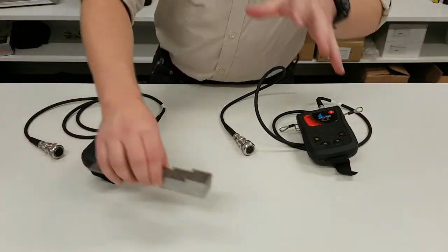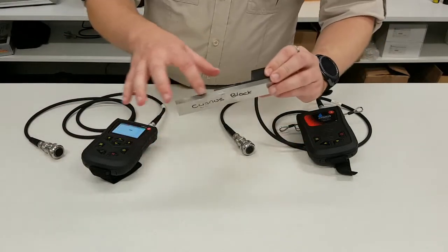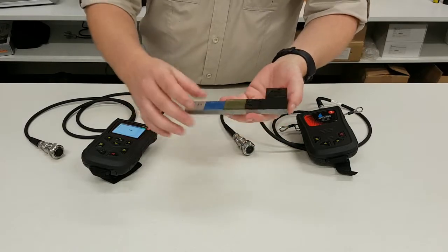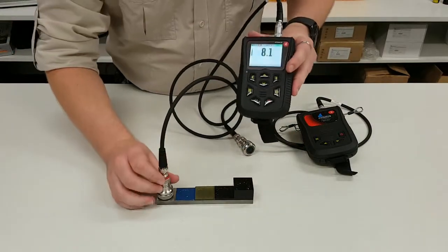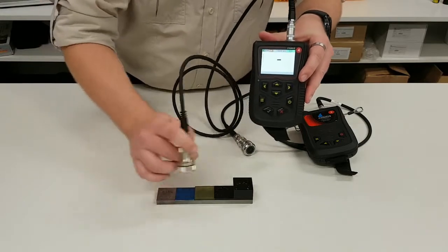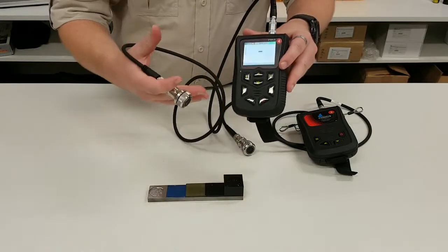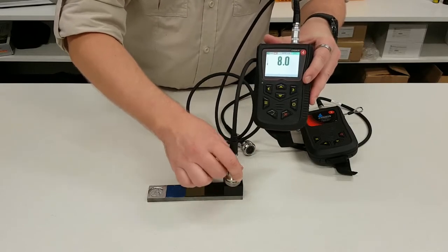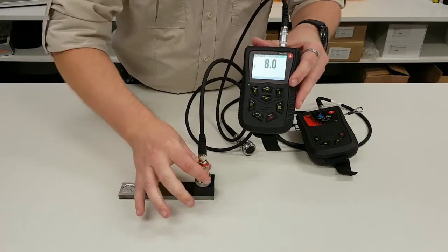Cygnus also has a feature called through-coating measurement, or multiple echo measurement. This allows it to measure through coatings up to 20mm thick. Here we have an 8mm block with a few different coatings of different thicknesses on the top. The gauge measures 8mm on bare steel, 8mm on the first coating, and 8mm on a thicker coating again. If you activate deep coat mode, you can measure through a really thick coating — this sample is about 20mm thick, and as you can see, it is still only measuring the steel underneath.